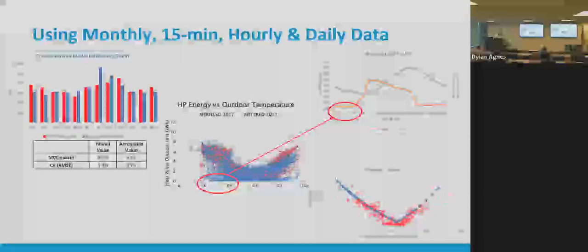One of my favorite ways is just to roll it up to daily, and sometimes zooming it out a bit helps tell the story. So this is daily total kilowatt hours - it's even better when you normalize it by square footage - daily kilowatt hours compared to average daily outside air temperature, and this creates this nice V, modeled versus actual. So those are a few different ways you can use field data to help calibrate simulations.